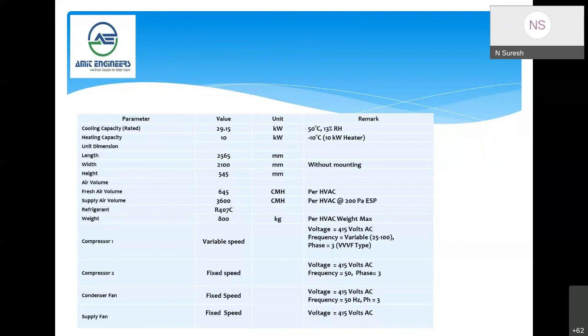And what is the benefit of a variable speed compressor? Here, to modulate the cooling capacity. Based on the temperature difference between the supply air and the return air, the speed of the compressor can be varied, and definitely a reasonable amount of energy saving is possible. So here there will be two compressors in this system. One will be a fixed compressor that will work at the normal designed cooling capacity. The other one will modulate. And there are two condenser fans, as I briefed earlier. To remove the heat from the condenser, there are two axial fans which take the ambient air through the condenser coil and reject the heat exhaust basically.